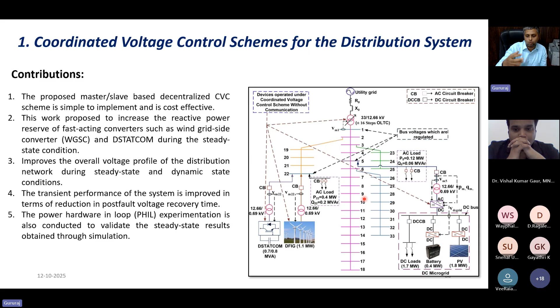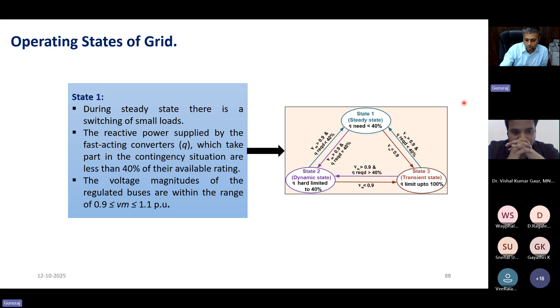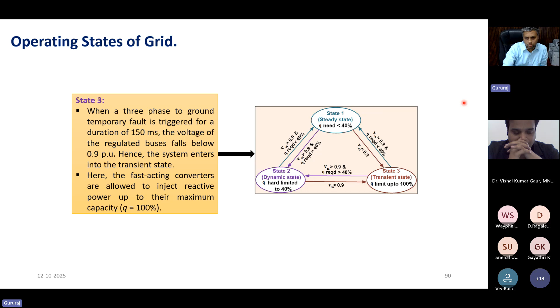So we have defined 3 different states: a steady state where the reactive power requirement expected from the fast acting converters is considered to be less than 40% of their available capacity. And in the dynamic state, though the reactive power requirement is increased because of switching on some dynamic loads like motor loads, we hard limit it to 40% to ensure that a bare minimum reactive power margin is available for the transient situation. And the transient state, where the 100% reactive power capacity available from the converters is used for the fault ride through behavior. So these are the 3 states that we have defined: steady state, dynamic, and transient state.